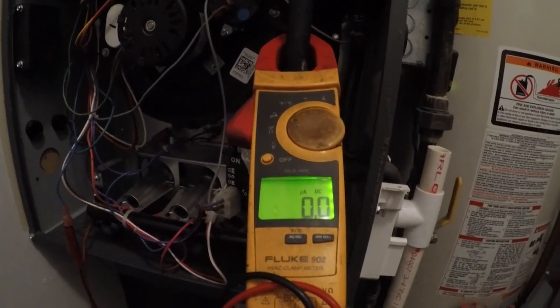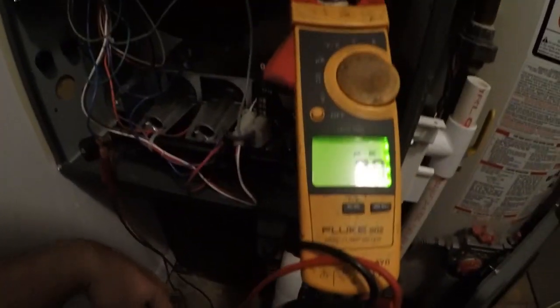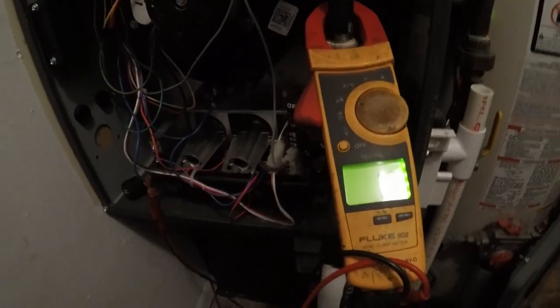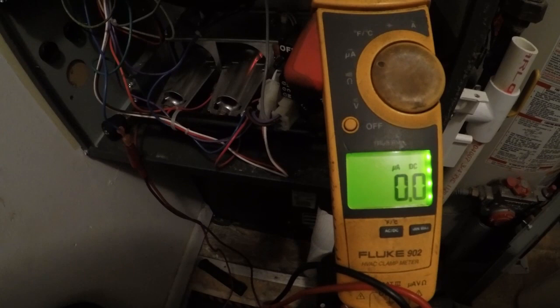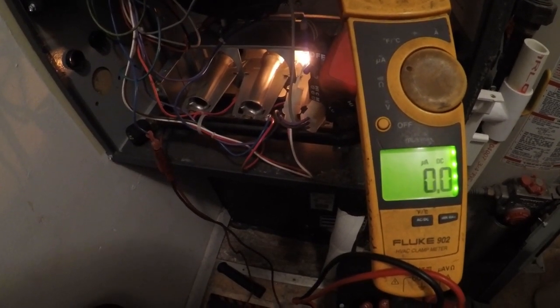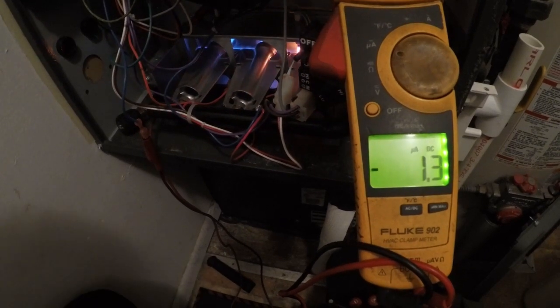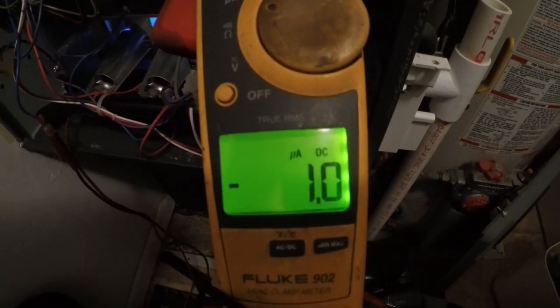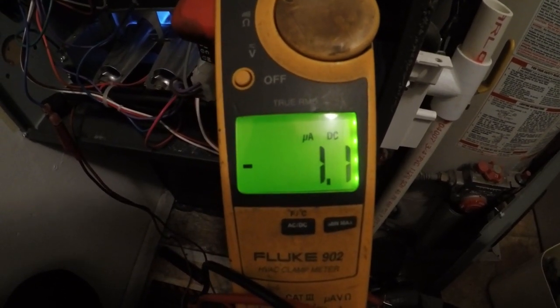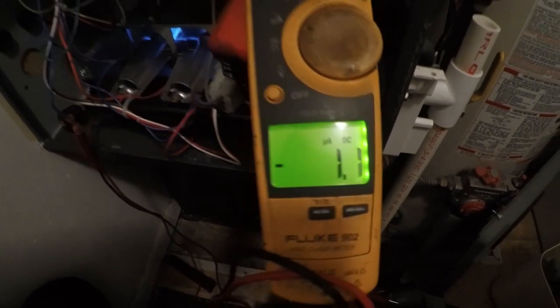I'm going to hook one jumper to the flame sensor wire and one to the flame signal. This is where the flame signal is. We're going to read the microamps on this flame sensor while it's running. We're reading 1.1 DC microamps. Typically we want that above 2, 3, sometimes 5, depending. So I'm going to go ahead and pull it out and clean it.